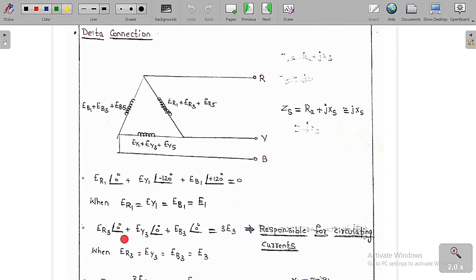For the third harmonic component, ER3 at 0 degrees, EY3 at 0 degrees, and EB3 at 0 degrees, since third harmonic components are all in the same direction, their summation is never equal to 0. It equals 3 times E3, because ER3 equals EY3 equals EB3 equals E3.